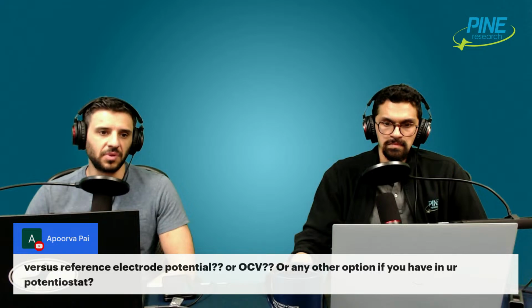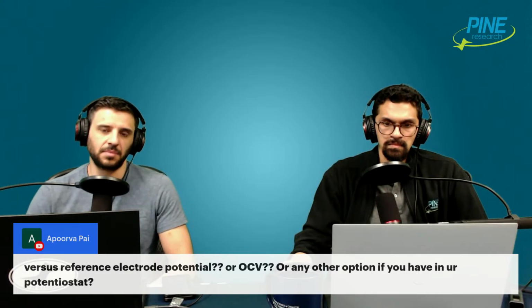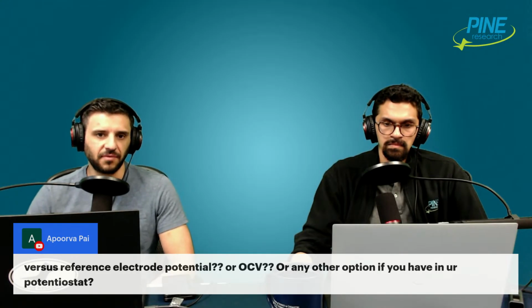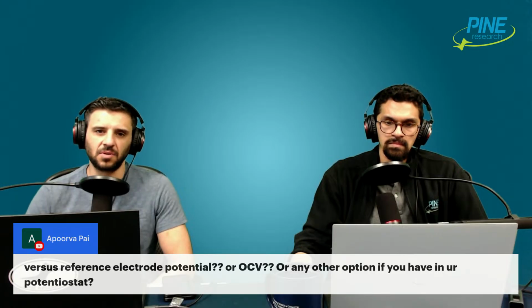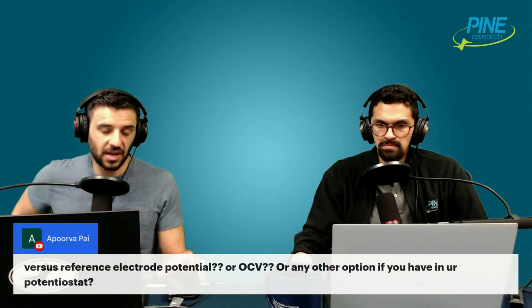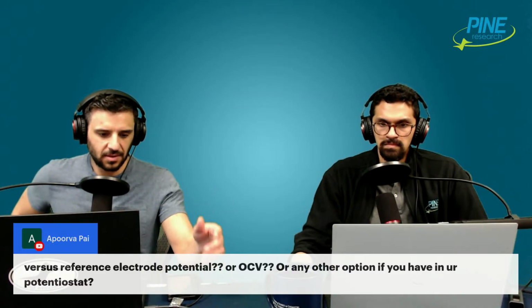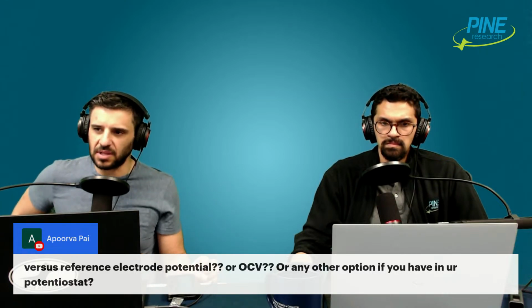So when you tell it to apply 250 millivolts, and then you also tell it to do that versus silver chloride or something, you're just telling it to apply whatever, 400 something, because it's just going to do the math for you. That's your job. It's not the potentiostat's job to do that, fundamentally. I just generally disagree with that. So the first thing I'd say is that if your software has the ability to make you pick what the reference is, I don't know that that's wise.